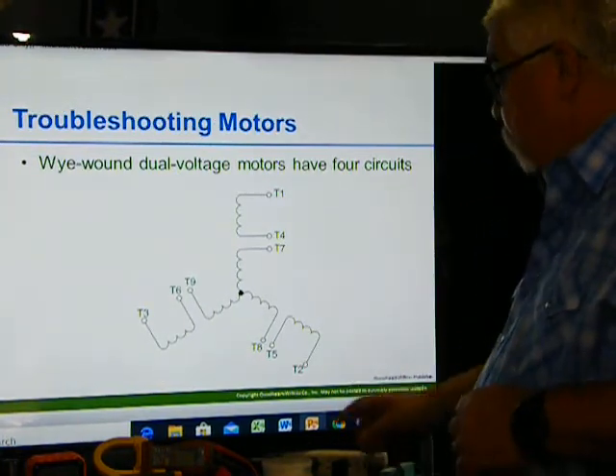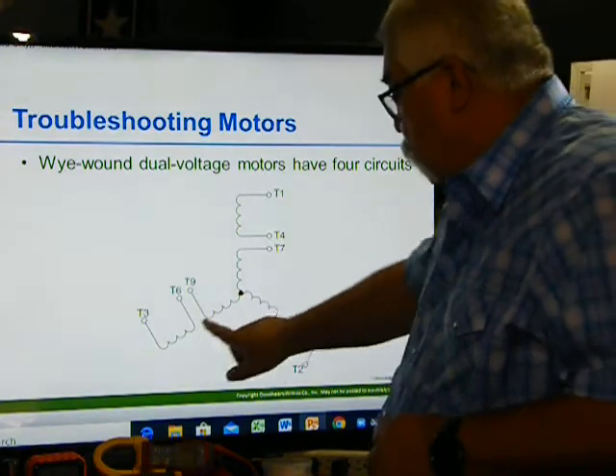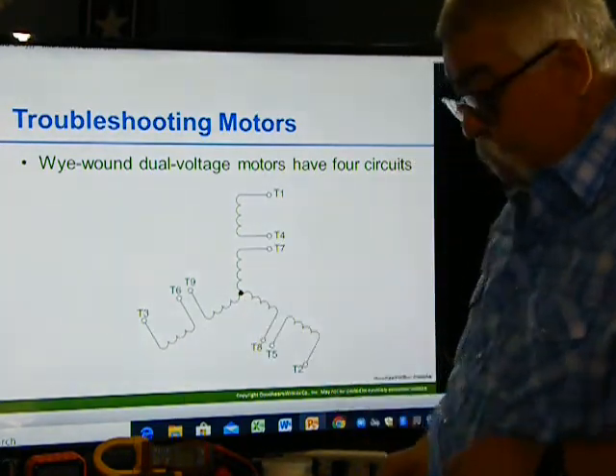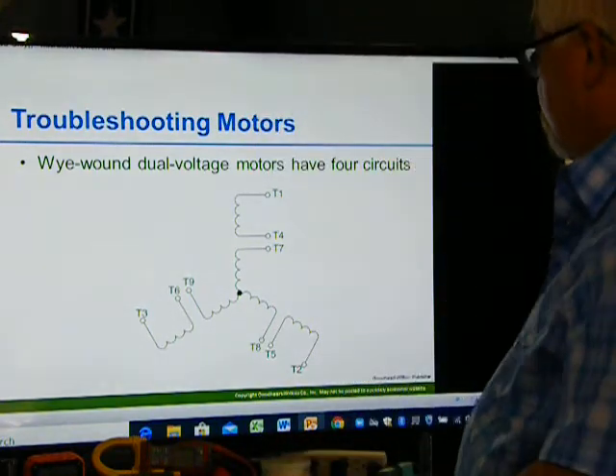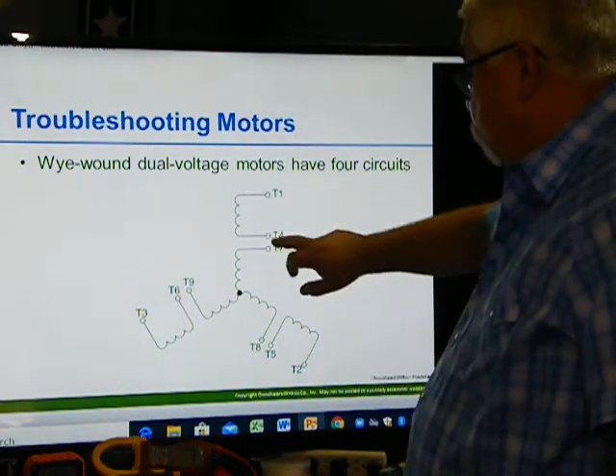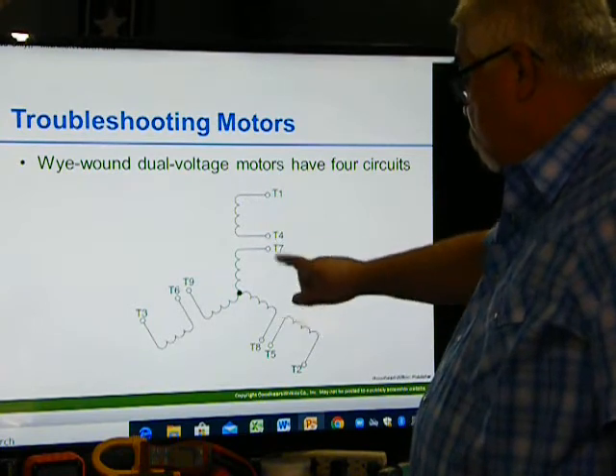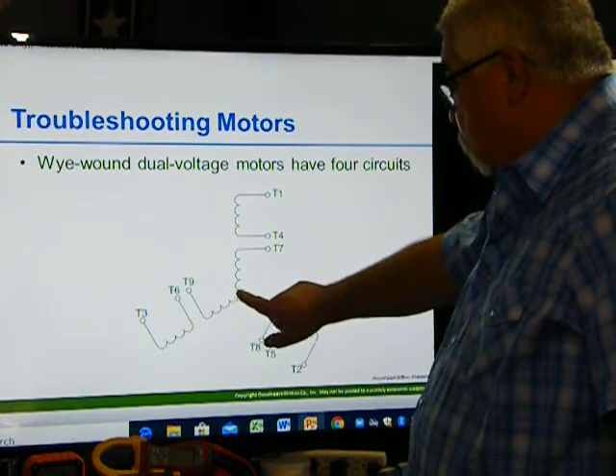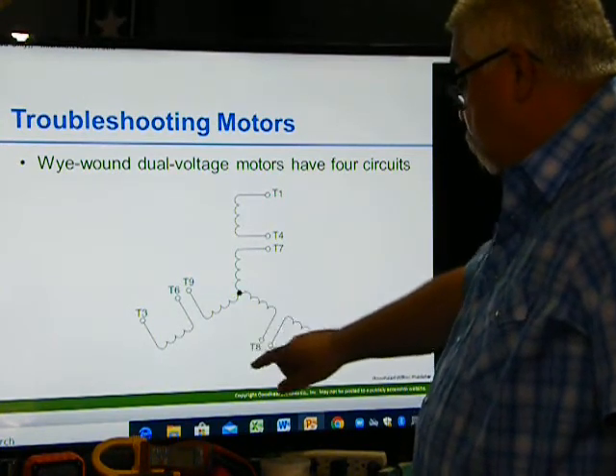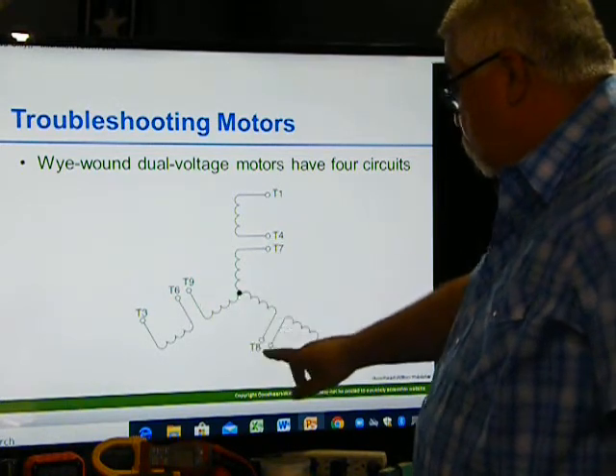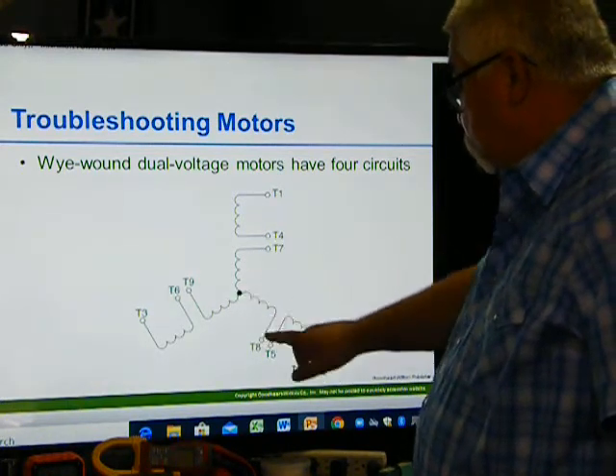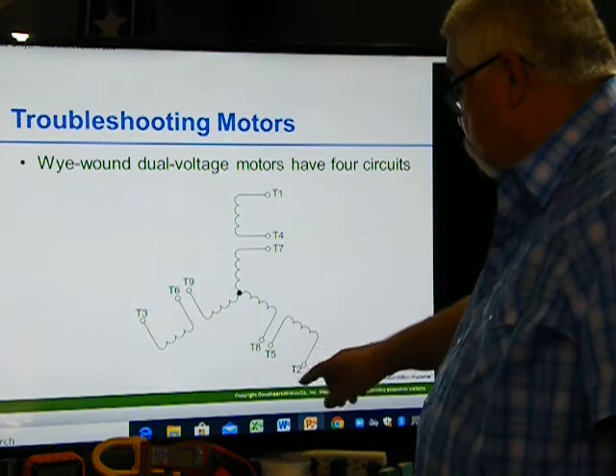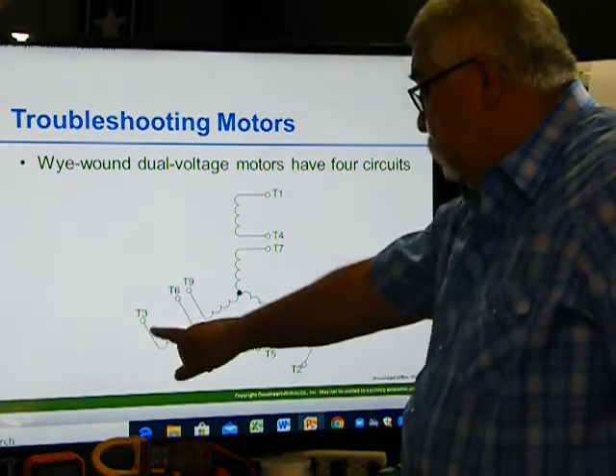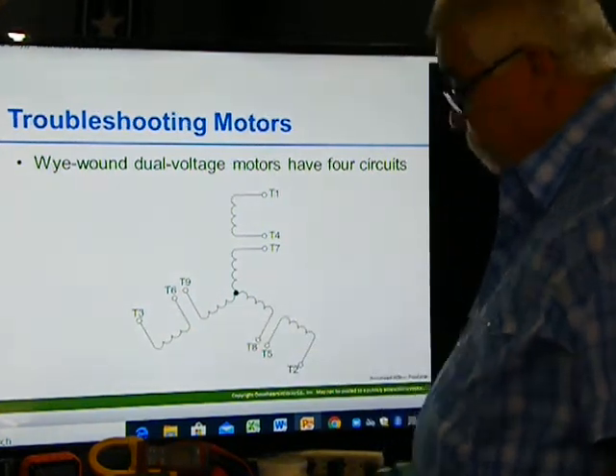So as you can see here, here's my Y. You can see that 1 and 4 are tied within the same winding, and then there's a common connection in the Y in the center. So 7, 9, and 8. Okay, and they make the tie here. So this is my Y. 2 and 5, 3 and 6.